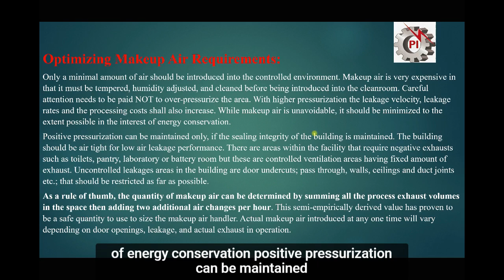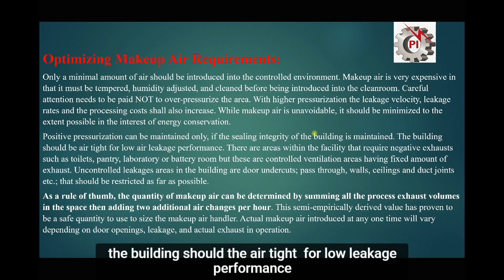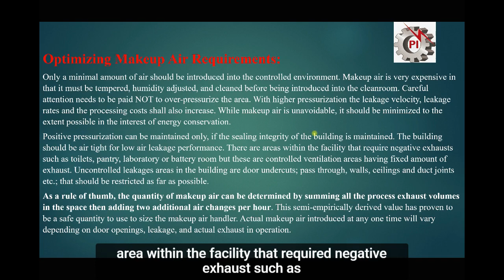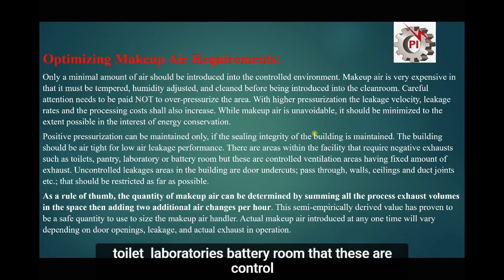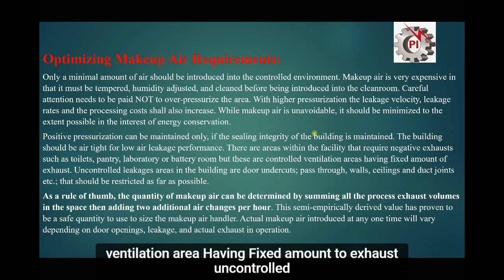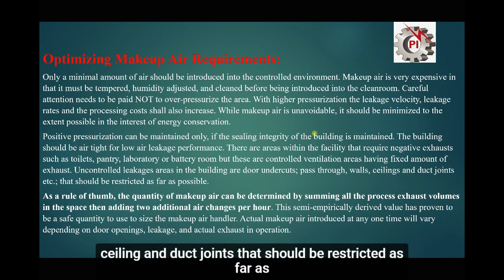Positive pressurization can be maintained only if the sealing integrity of the building is maintained. The building should be airtight for low leakage performance. There are areas within the facility that require negative exhaust, such as toilets, pantry, laboratory or battery room, that are controlled ventilation areas having a fixed amount of exhaust. Uncontrolled leakage areas in the building are doors, undercuts, pass-through walls, ceiling and duct joints. That should be restricted as far as possible.